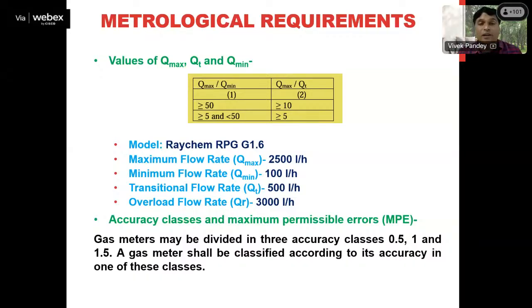According to the second row, Q max to QT should be greater than or equal to 5. And in our case, it is 5, because Q maximum is 2500 liter per hour and Q transitional, QT, is 500 liter per hour. If you divide Q max by QT, you get 5. Fine. So both of these ratios are complying with the condition. That means these flow rates specified by the manufacturers are correct as per our regulation.